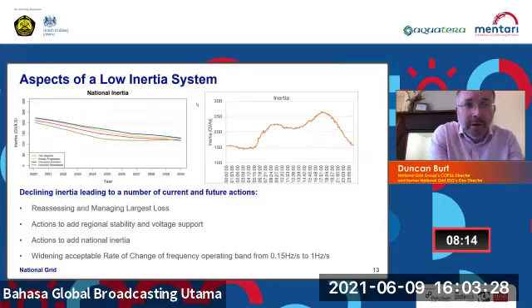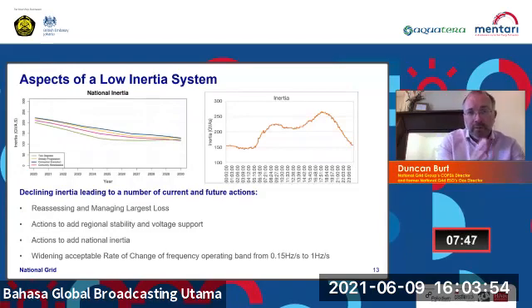The UK system at 50 gigawatt peak varies significantly during the day. So we peak in the afternoon in the winter at highest demand, and then some of those power stations come off overnight, and overnight we tend to sit around 150 to 200 GVA historically. And that will go down and down and down. Our natural limit at the moment sits around 100 GVA, and we have to take measures to contain that in the short term. And then in the medium term, we have a whole series of measures that are already coming in that allow that inertia to go even lower.